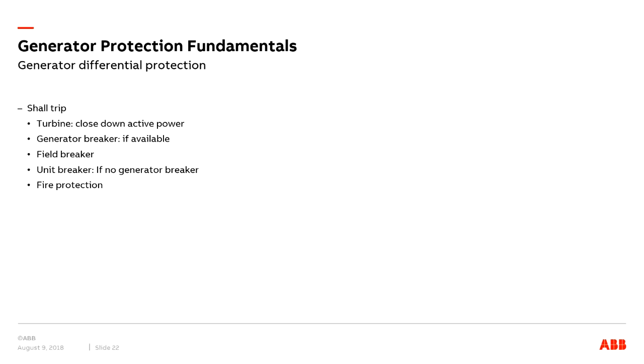Then we need to trip the field breaker. This is important in order to reduce the fault current from the generator itself. The trip signal to the generator breaker is important in order to reduce the fault current from the external network. In many power plants, there is no generator breaker, only a unit breaker at the high voltage side of the unit transformer. So we trip the unit breaker in the case a generator breaker does not exist. If the generator breaker exists, the unit breaker should not be tripped, as there should be a possibility to maintain the connection to the auxiliary system via the auxiliary transformer connected between the generator breaker and the unit transformer.